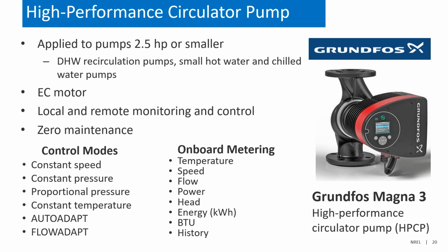Normally for circulator pumps, these are constant volume. The older ones use an inefficient induction motor. So here you can see these are applied to pumps that are about 2.5 horsepower or smaller. The primary application of them are domestic hot water recirculation pumps. You'll also see a lot of them for air handling unit booster pumps, for either the air handling unit heating coil or the cooling coil, or for radiant baseboard heating. So these are the smaller circulator pumps that serve miscellaneous loads within your facilities.